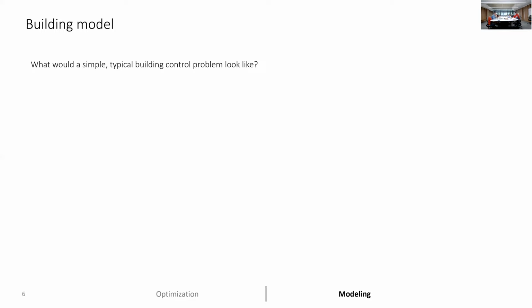Let's start with obviously a simple one, but we have what we define as comfort costs and operation costs, basically, of the building here in this case. And we want to minimize those over T, which are the time steps we consider. And H here is what we call the horizon of the problem. So that's the set of time steps that we're trying to solve our problem for. I'll mention here that the superscript D refers to decision variables. So these are parts of the variables that the problem is going to be able to adapt to get the best outcome possible.